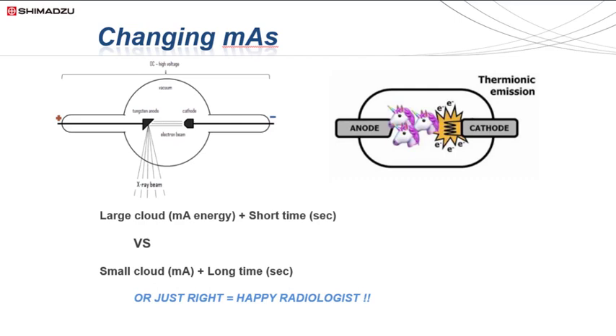Let's back up and revise what we know about x-ray generation. An electron cloud is generated at the cathode — the size of the electron cloud depends on how high the MA is. The energy is discharged towards the focal spot on an anode and an x-ray beam is created. Imagine the electron cloud as a herd of unicorns: when released like at the start of a horse race, they move out of the barriers all at the same time with speed and power. But if the finish line is reduced to a small narrowing like a gate, not all unicorns can get through at the same time — and hence, like a large electron cloud, not all the power and speed can be captured and the resultant x-ray beam will be less efficient. This is what happens with large MA and short exposure time, and is also the cause of reduced tube life as the anode is increasingly overheated by a large electron cloud.